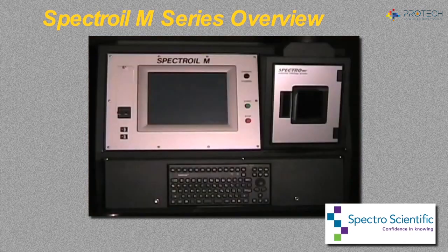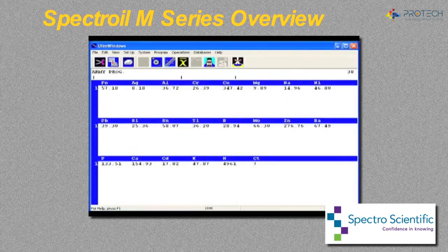Spectrometric oil analysis is applicable to any closed-loop lubricating system, such as those found in diesel and gasoline engines, gas turbines, transmissions, gearboxes, compressors, and hydraulic systems. The spectrometer analyzes the sample for trace levels of metal worn from moving parts, as well as for extraneous contamination and additive element levels.